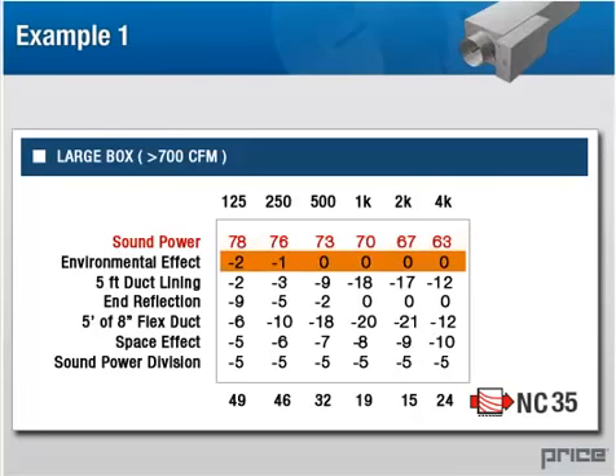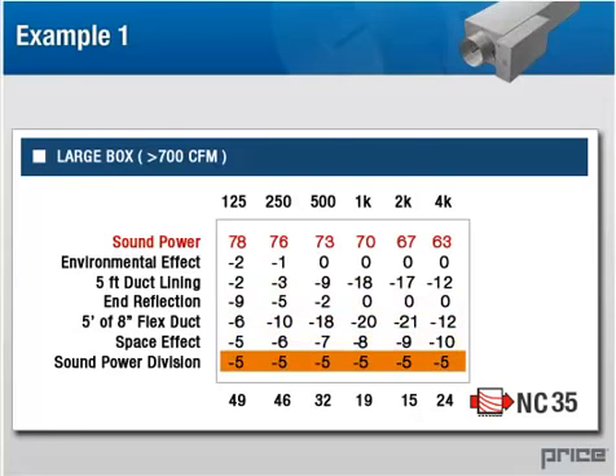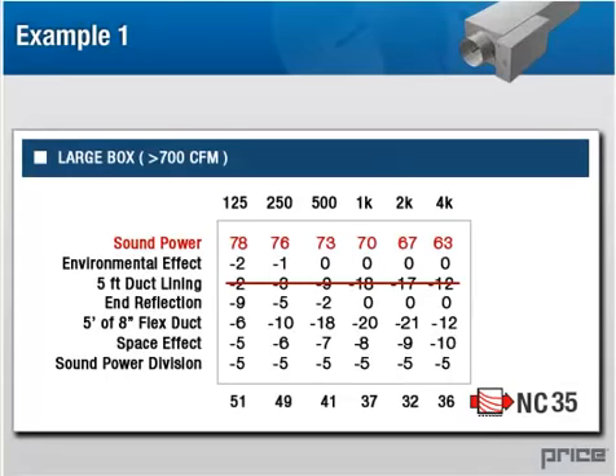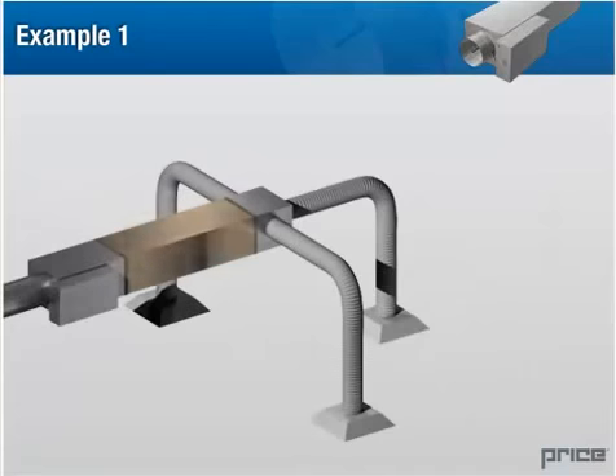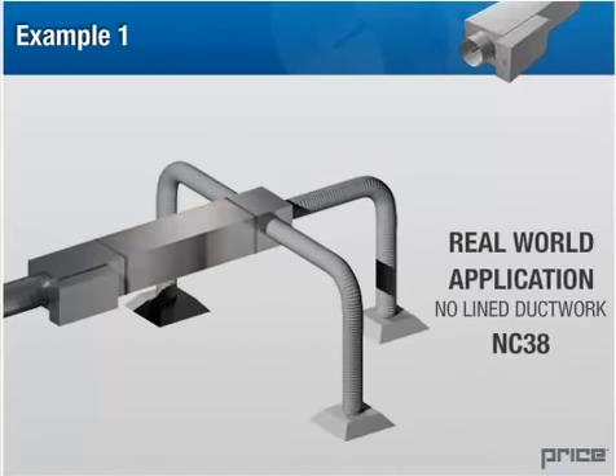Looking at the attenuation values for a large box, we can see that there are several values that are used to generate the NC level of 35 at the maximum CFM capacity of the size 12 unit. If we were to remove one of these values to match our actual job site condition, like the 5 feet of duct lining after the terminal unit, we can see the effect that it'll have on our discharge NC level. So if the project in this example does not include lined ductwork, we have accidentally selected a terminal unit that does not meet the noise requirement.